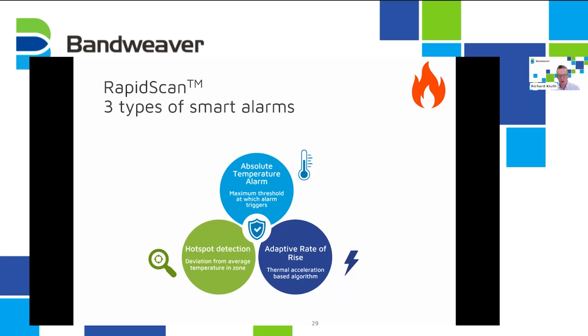So often I get asked by customers, what values should we set? And it's very much dependent on each installation. But we do see patterns where, I'd say, 80 to 90% of customers use very similar alarms. For the absolute temperature, it's typically 30 degrees above maximum ambient temperature. So in Northern Europe, where the typical maximum is 30 degrees, people would set the temperature at the high 50s or 60 degrees C. In the Middle East or Asia, it may go a bit higher than that. And often the regulations dictate that you need to set the threshold 30 degrees above ambient.